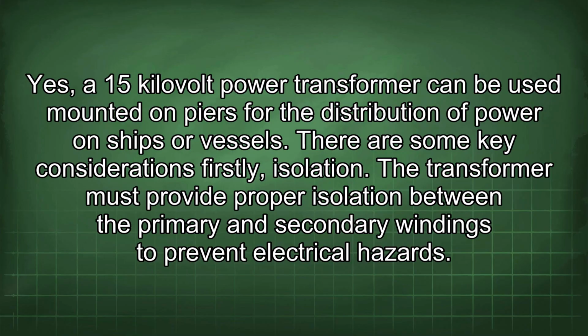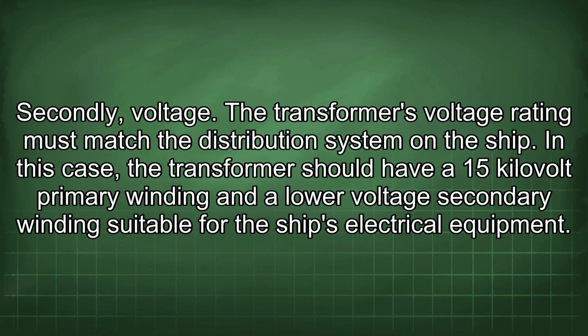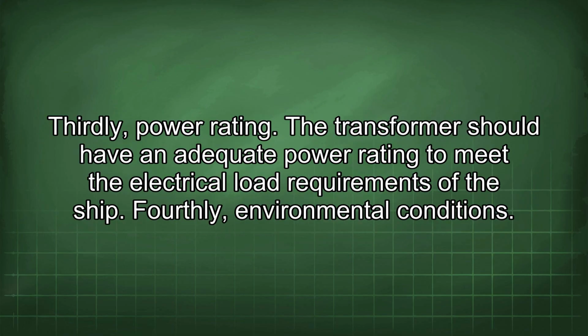Yes, a 15 kilovolt power transformer can be used mounted on piers for the distribution of power on ships or vessels. There are some key considerations. Firstly, isolation. The transformer must provide proper isolation between the primary and secondary windings to prevent electrical hazards. Secondly, voltage. The transformer's voltage rating must match the distribution system on the ship. In this case, the transformer should have a 15 kilovolt primary winding and a lower voltage secondary winding suitable for the ship's electrical equipment. Thirdly, power rating.